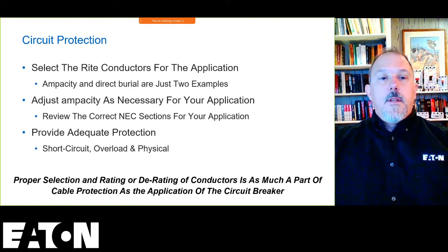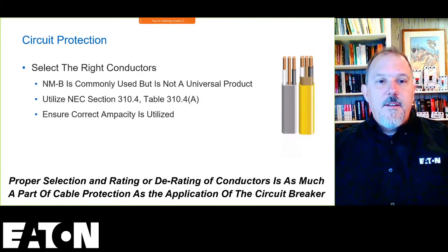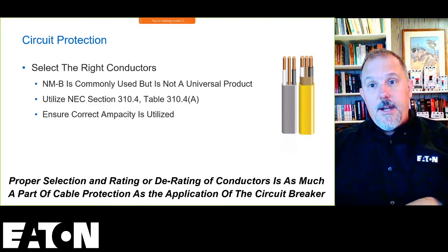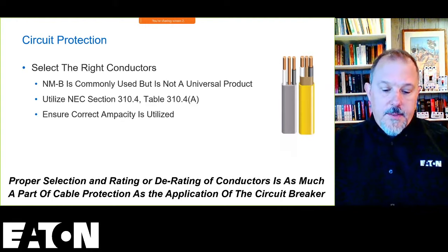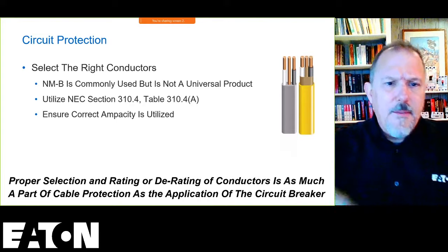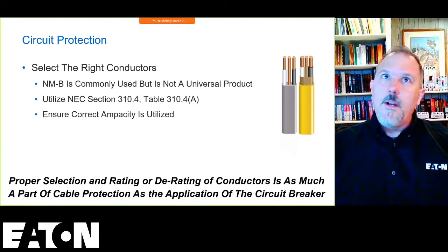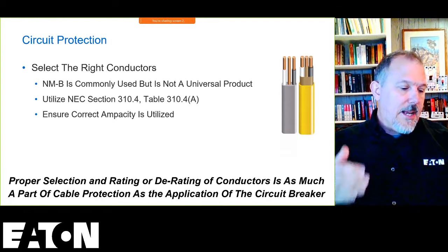All right, so let's talk about selecting the right conductor. We use NM wire a lot, but it's not the universal product that goes everywhere. We have tables in 310 that we leverage, and I think it's 310.4. Yeah, 310.4, I got it right there.